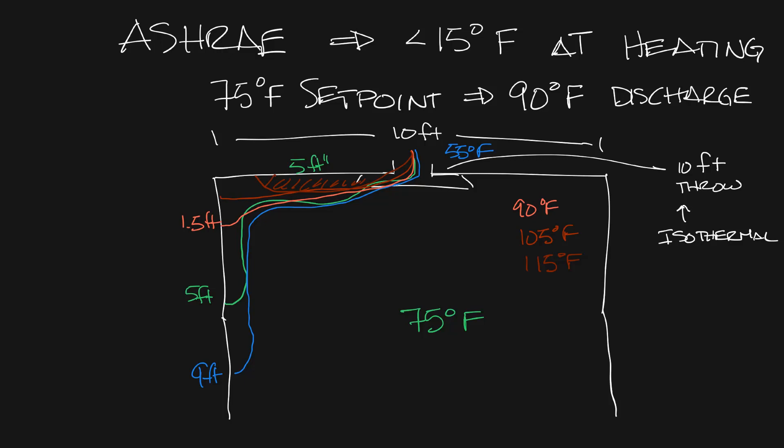So as you raise the supply air temperature you shorten the throw and so now you're not getting much mixing out of your diffuser and that's how you make the air in the space warm. So your air in your space is going to stay colder if you put hotter and hotter air into your diffuser.